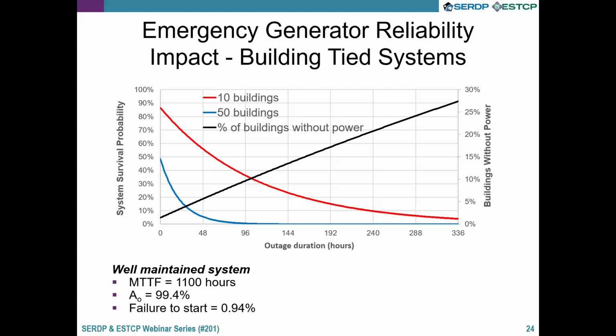What you see is that although a single generator might have a 75% chance of continuing to run out to 2 weeks, once you have multiple independent ones, those probabilities cascade. So if you had a 50 building system, within 2 days the probability that all your critical loads are supported is close to zero. Even with a small base of only 10 buildings with critical loads, it drops quite a bit. The black curve shows what fraction of buildings are without power. Some buildings will always have power, but over 25% don't.